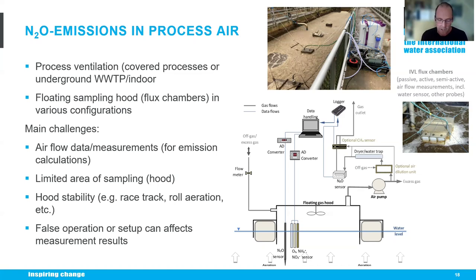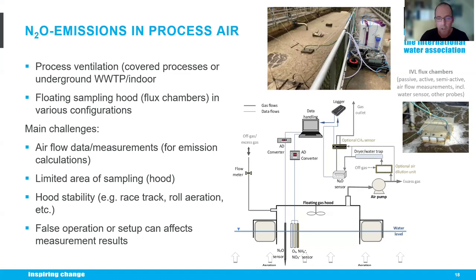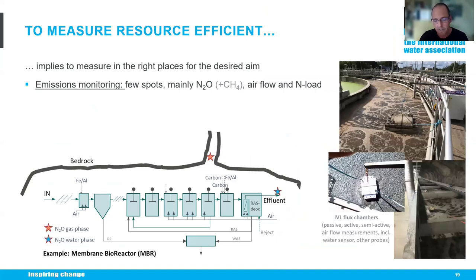As emissions measurement is resource intensive, it's important to apply measurements at the right place. For overall emission monitoring, there may be only a few spots needed, mainly measuring N2O, methane, airflow, and load. For example, the main wastewater treatment plant in Stockholm — which is inside rock — measuring in the ventilation shaft and with the water sensor at the effluent gives quite good emission monitoring. However, if you want more control and mitigation, you need measurements at several spots.